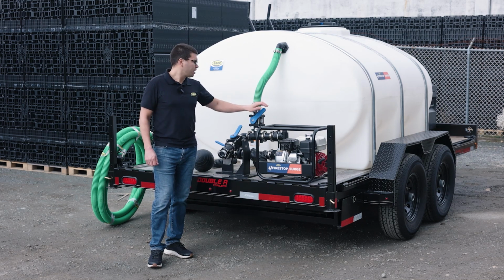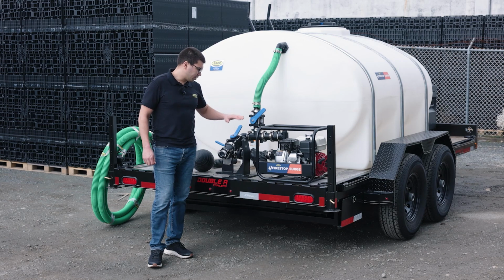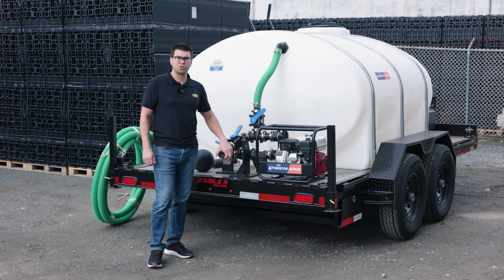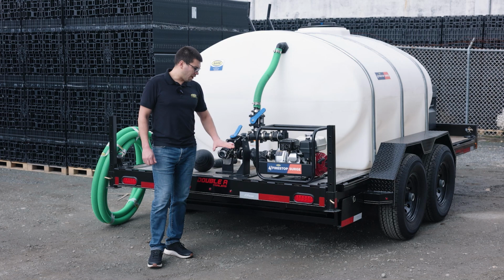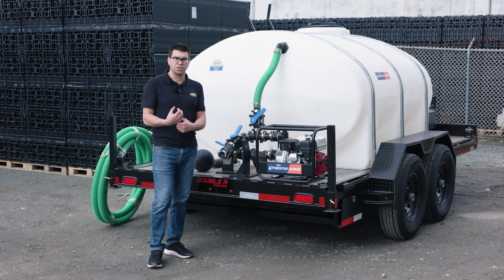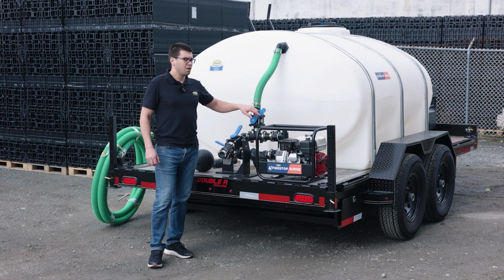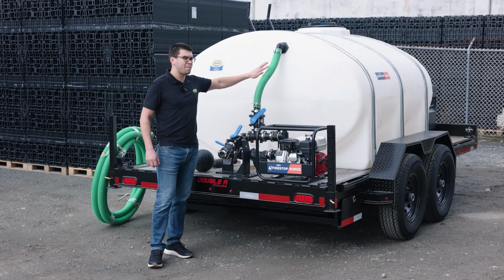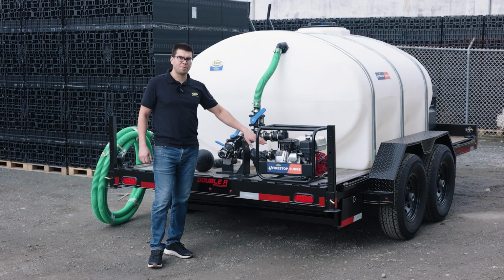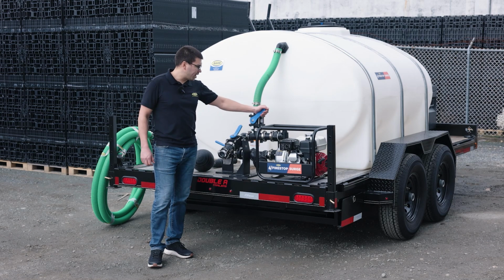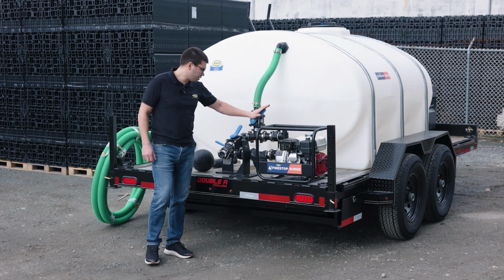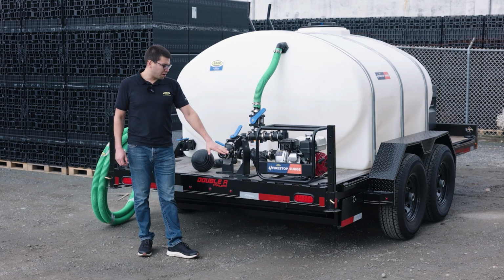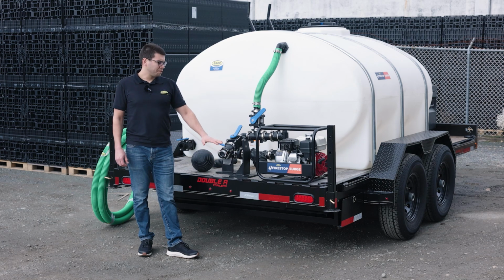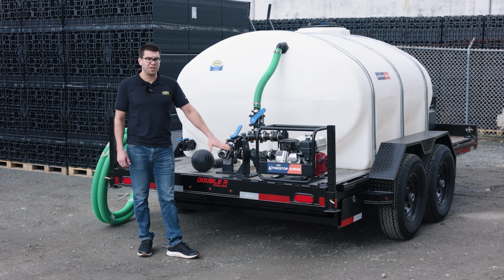pressure valve a little bit. And what that does is, let's say we are discharging water through the fire hose connection. If we turn the end nozzle off, the pressure bypass will allow some pressure to get back to the tank. So we're not pressure spiking the pump head, because that can damage and crack the pump head. So in this case, we'll close that partially open, and then you're shooting out of your fire hose. And like I said, it will shoot about 80 feet to a 50-foot fire hose.